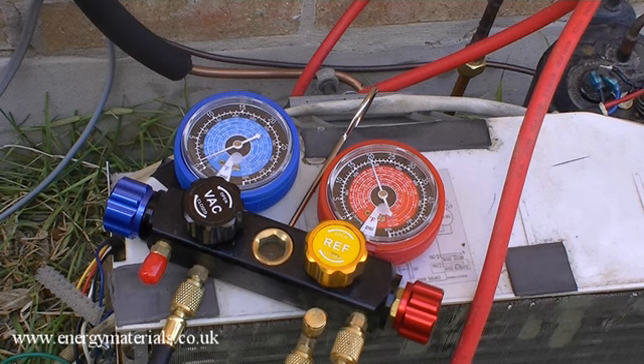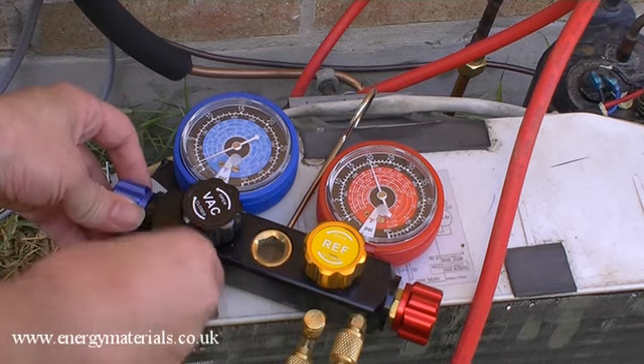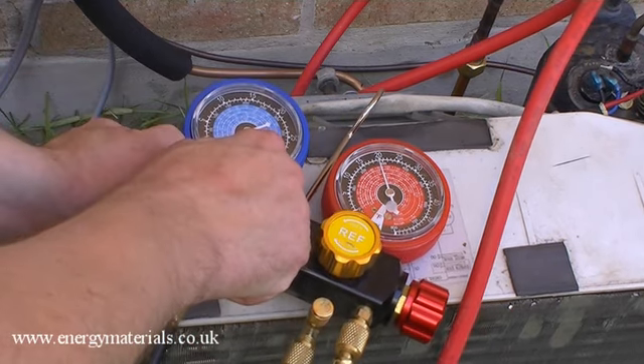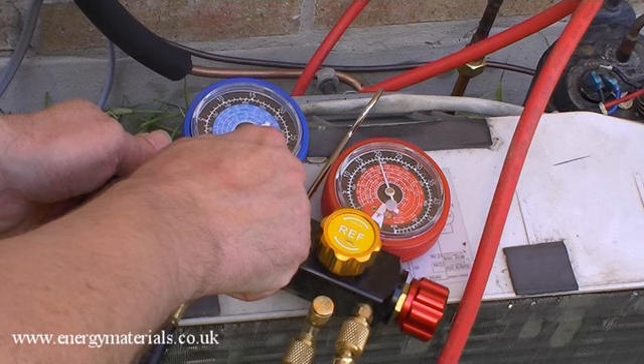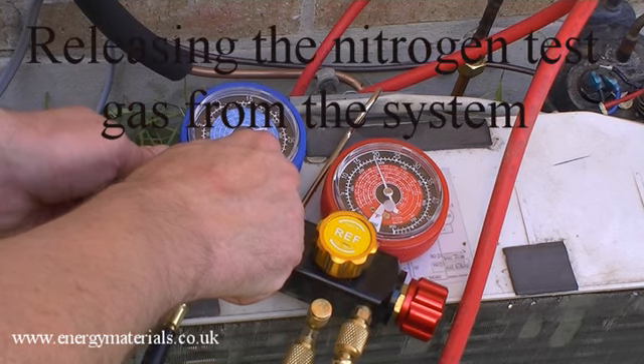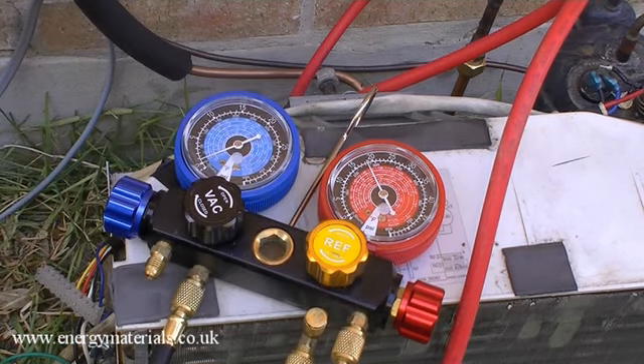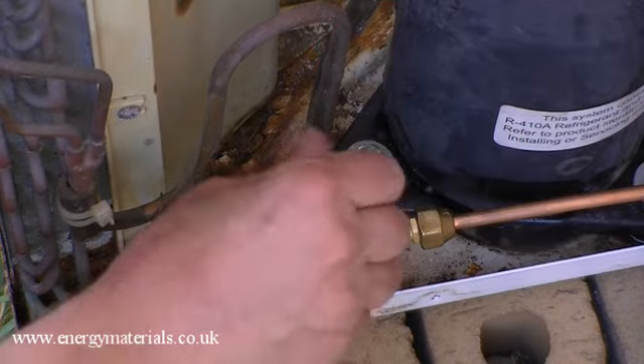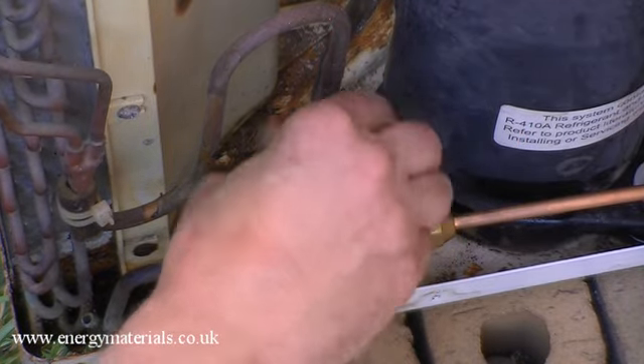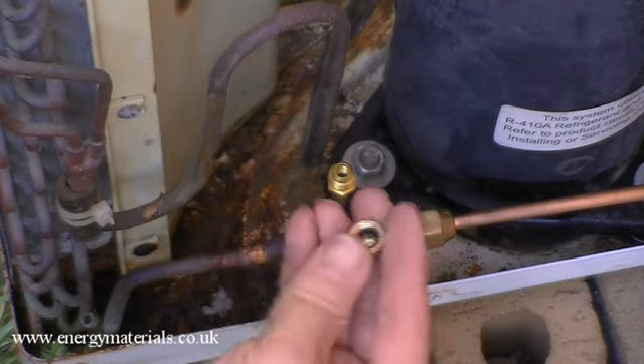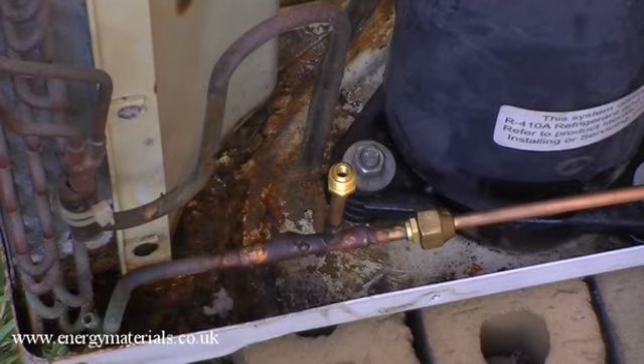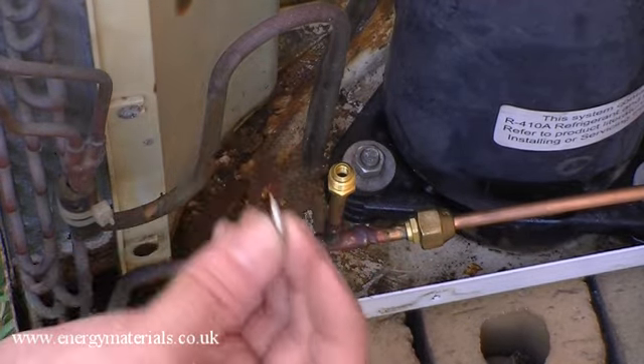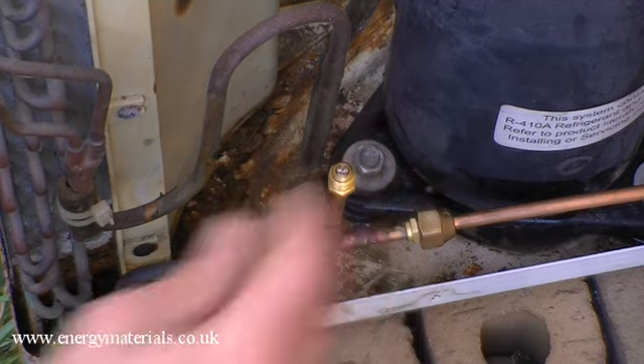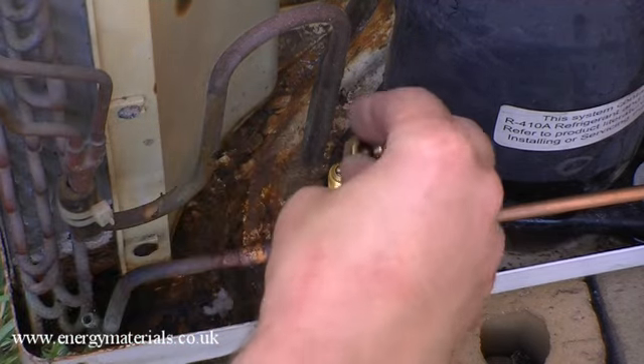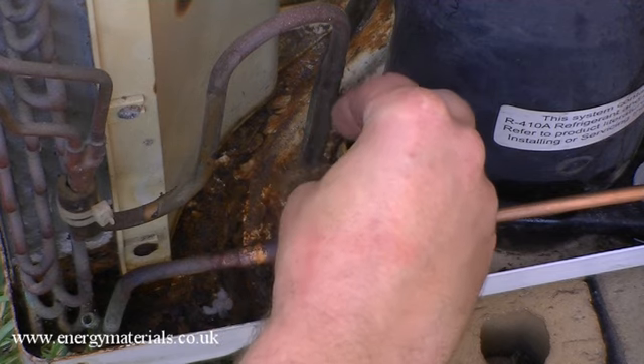So what I'm going to do now is depressurize the system and put in the Schrader valves. So I'm going to discharge it through this port. Okay, so this is the port where the Schrader valve goes in. Unscrew this cap. See, the cap's got an O-ring on there, the sealing. Obviously the valve was removed for brazing, so it's got an elastomer on the seal, so we're going to pop him in there. Using the end of the cap, which is quite a nice design, rotate that in.